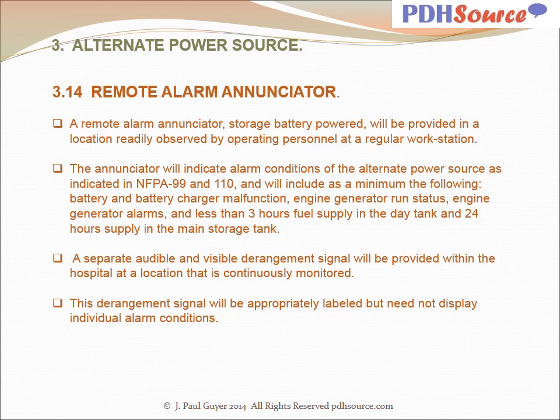A remote alarm annunciator, storage battery powered, will be provided in a location readily observable by operating personnel at a regular workstation. The annunciator will indicate alarm conditions of the alternate power source as indicated in NFPA 99 and 110, and will include as a minimum the following: battery and battery charger malfunction, engine generator run status, engine generator alarms, and less than 3 hours fuel supply in the day tank, and 24 hours supply in the main storage tank. A separate audible and visible derangement signal will be provided within the hospital at a location that is continuously monitored. This derangement signal will be appropriately labeled, but need not display individual alarm conditions.